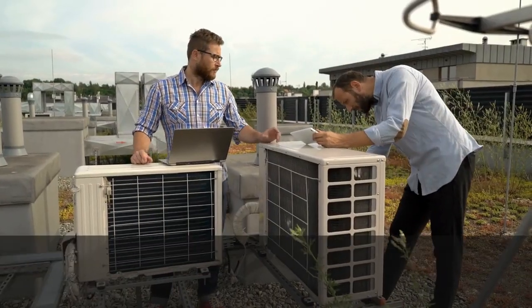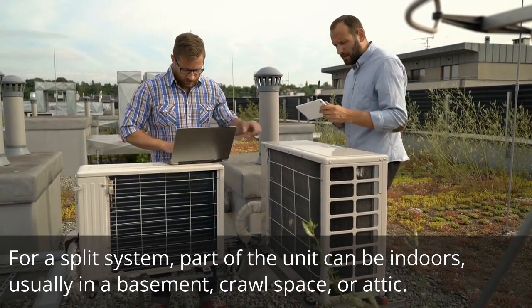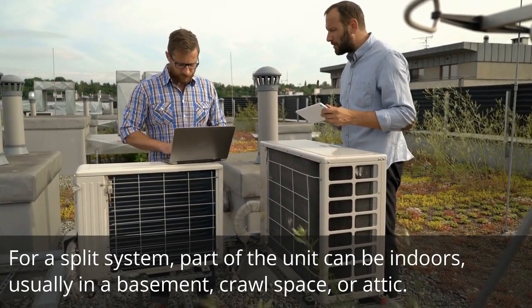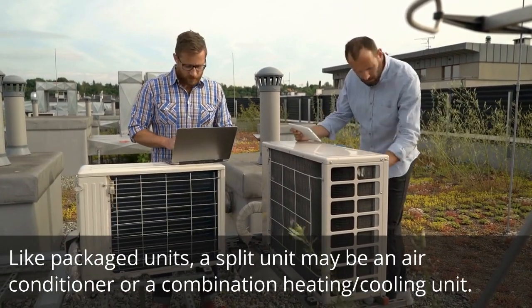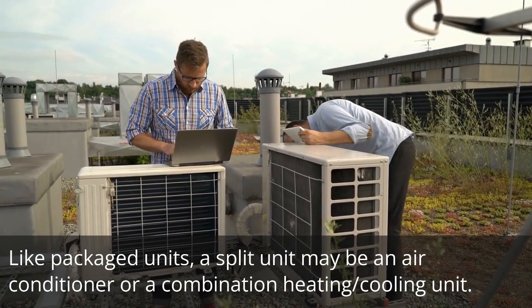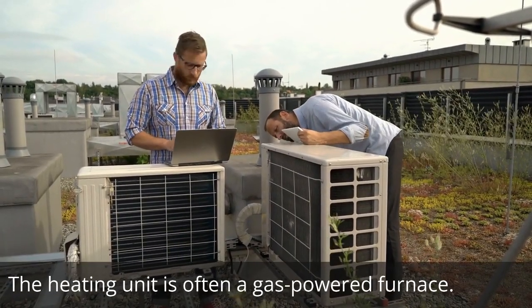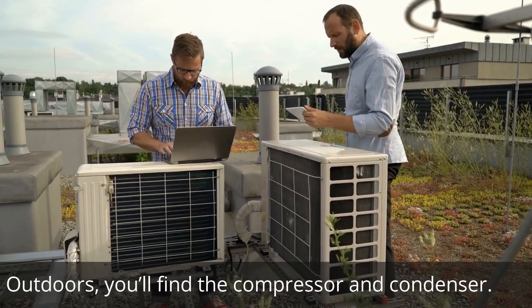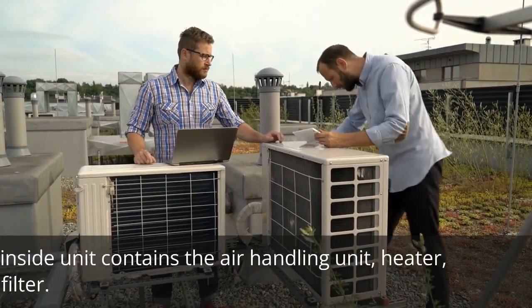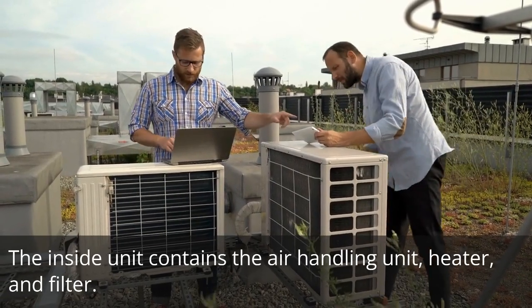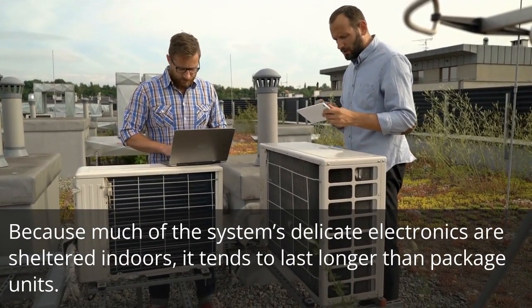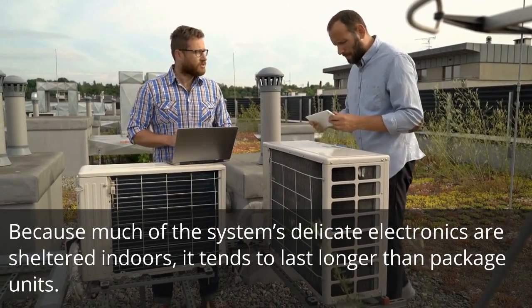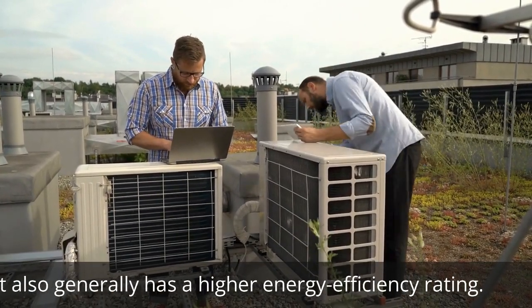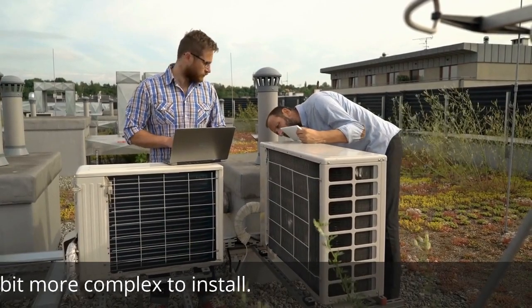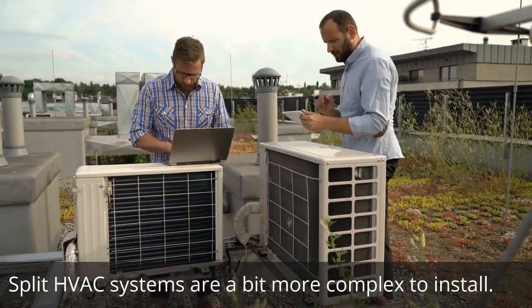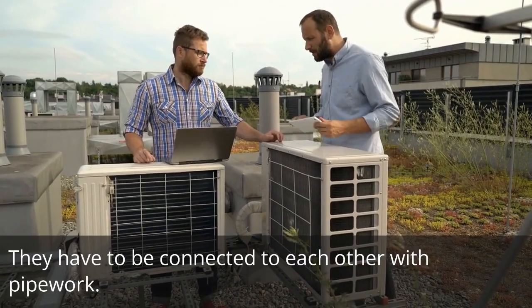Split HVAC systems. For a split system, part of the unit can be indoors, usually in a basement, crawl space, or attic. Like packaged units, a split unit may be an air conditioner or a combination heating/cooling unit. The heating unit is often a gas-powered furnace. Outdoors, you'll find the compressor and condenser. The inside unit contains the air handling unit, heater, and filter. Because much of the system's delicate electronics are sheltered indoors, it tends to last longer than package units. It also generally has a higher energy efficiency rating. Split HVAC systems are a bit more complex to install. They have to be connected to each other with pipework.